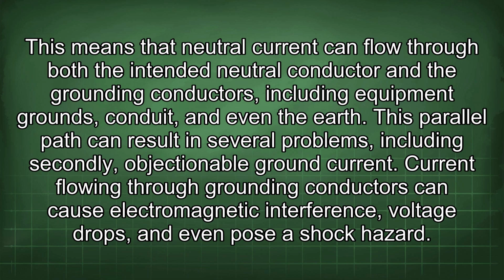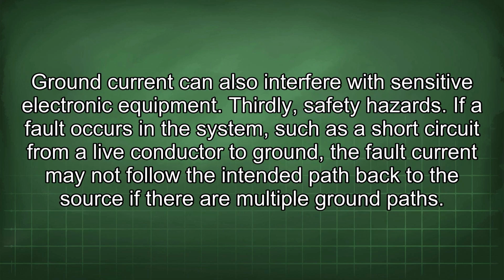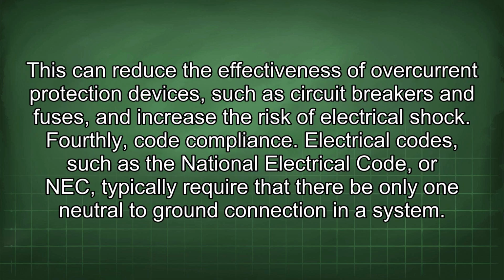Current flowing through grounding conductors can cause electromagnetic interference, voltage drops, and even pose a shock hazard. Ground current can also interfere with sensitive electronic equipment. Thirdly, safety hazards. If a fault occurs in the system, such as a short circuit from a live conductor to ground, the fault current may not follow the intended path back to the source if there are multiple ground paths. This can reduce the effectiveness of overcurrent protection devices, such as circuit breakers and fuses, and increase the risk of electrical shock. Fourthly, code compliance.